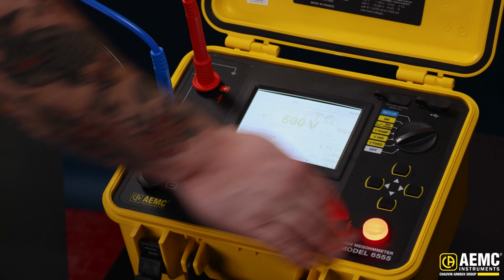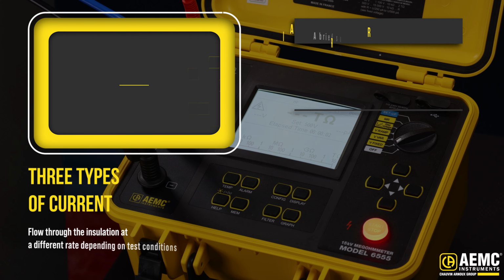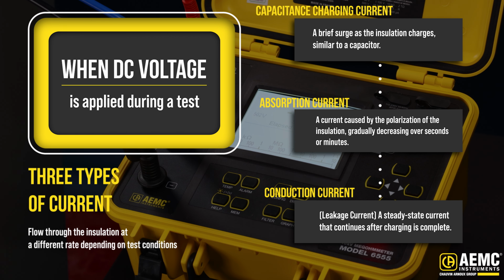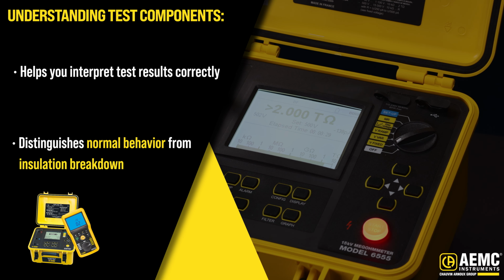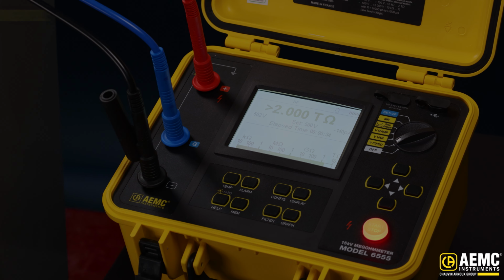When you apply a DC voltage during a test, 3 types of current flow through the insulation. Capacitance charging current, a brief surge as the insulation charges, similar to a capacitor. Absorption current, caused by the polarization of the insulating material, which decreases gradually over seconds or minutes. And conduction current, also known as leakage current, is the steady-state current that continues after charging is complete. Understanding how these components behave helps you interpret test results correctly, distinguishing normal behavior from insulation breakdown.